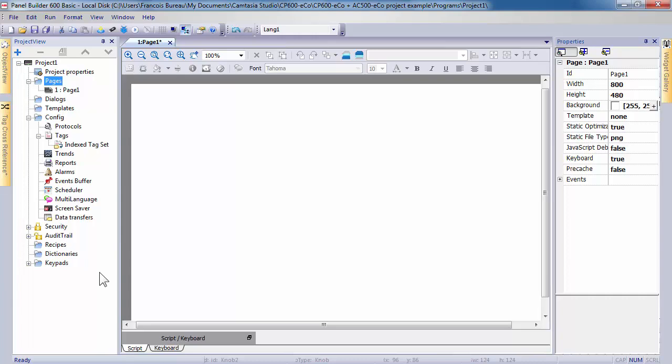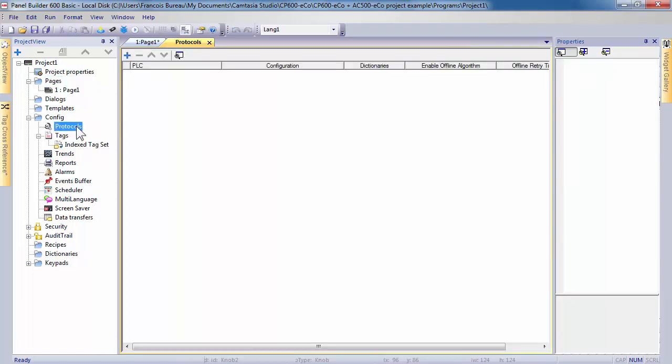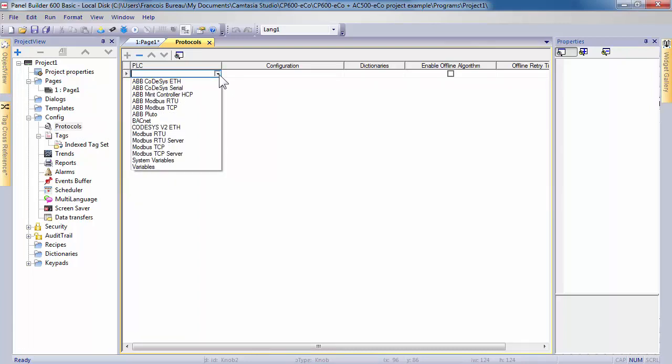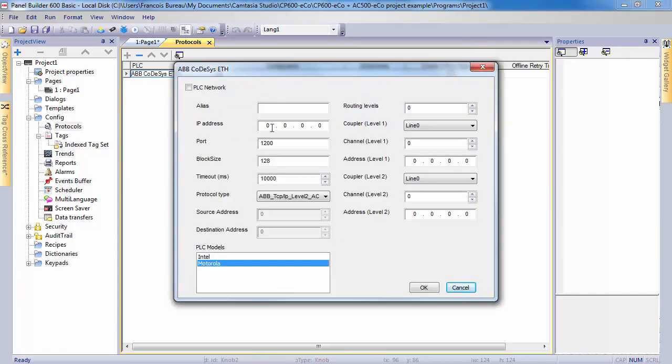We will now select a protocol. This is the first step before creating anything else. Double click on it to open the window parameters. Click on plus to access the selection of all device drivers available with CP600 eCo panels. In the drop-down list, select the desired protocol, ABB CodeSys Ethernet Driver, to be able to work directly with AC500 eCo variables configured in the symbol file.